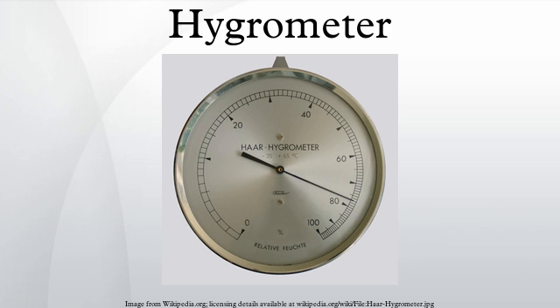The first practical hygrometer was invented by polymath Johann Heinrich Lambert in 1755. Types: metal paper coil type. The metal paper coil hygrometer is very useful for giving a dial indication of humidity changes. It appears most often in very inexpensive devices, and its accuracy is limited, with variations of 10% or more. In these devices, water vapor is absorbed by a salt-impregnated paper strip attached to a metal coil, causing the coil to change shape. These changes cause an indication on a dial.